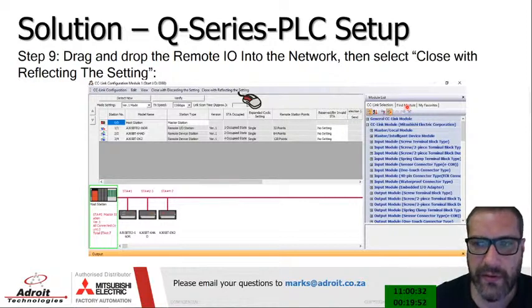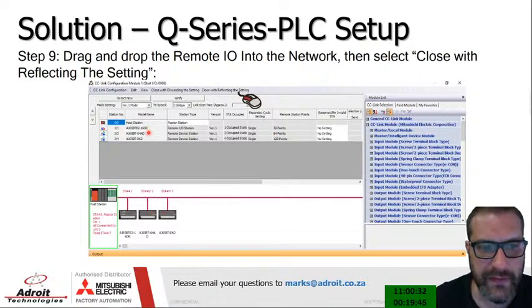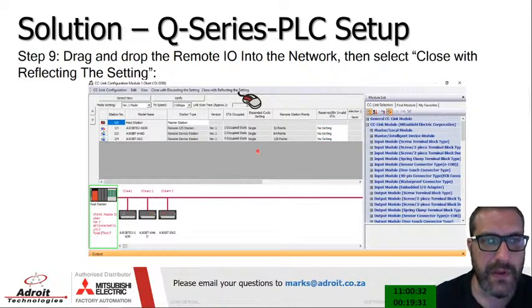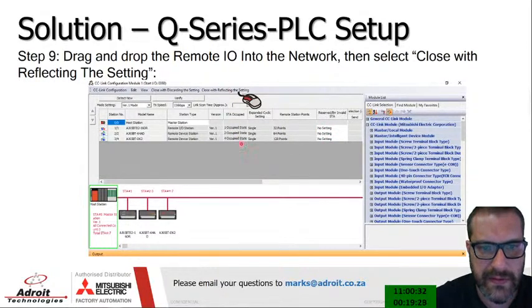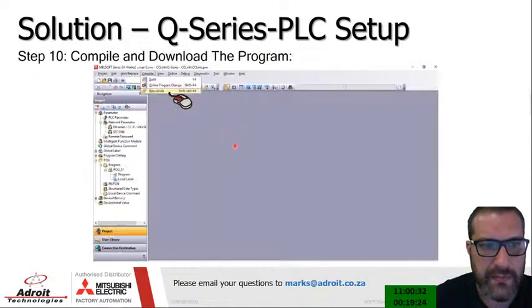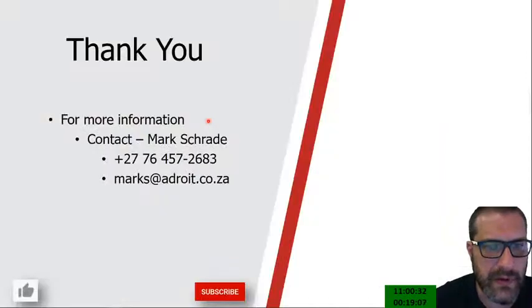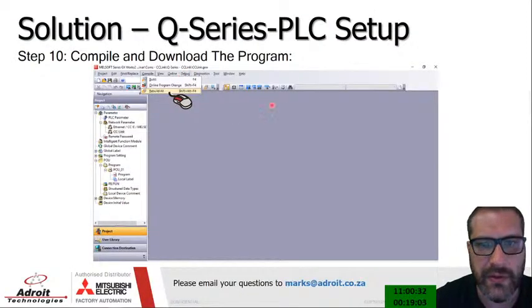The key setting is 'CC Link Configuration Setting.' Select it and you'll go to a configuration page. On the right side there is a 'Find Module' option where you can search for and find the specific device you want to communicate with in the field. Once found, simply drag and drop it into the configuration. Every time you add a device, drag and drop it in. When done, click 'Close with Reflecting the Setting' to save. Then compile the program via Compile > Rebuild All to check for syntax errors, and once clear, download the program to the PLC.